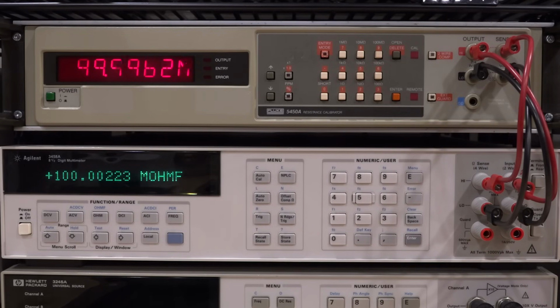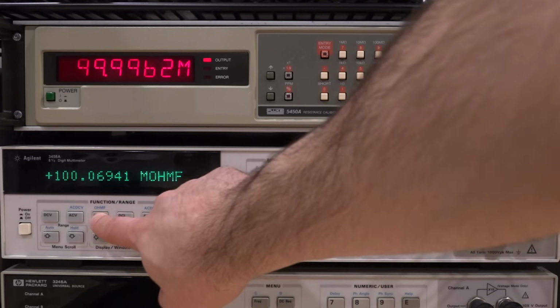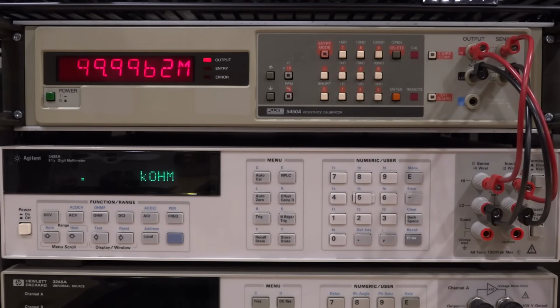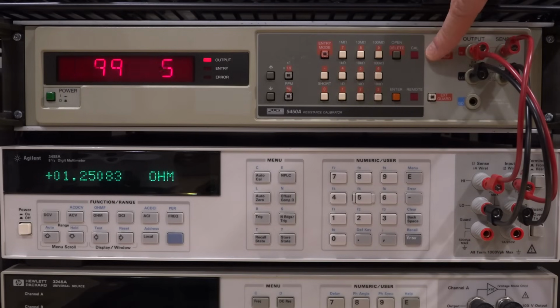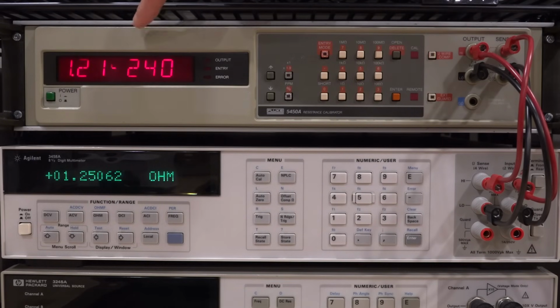This is a 4-wire measurement. We can also do a 2-wire measurement, but it shouldn't matter at this 100 mega ohm range, of course. There it is. You can settle it down. But if I go to 1 ohm, that will make a difference. You can see it should be over 1. There it is, 1.25. But if I enable the 2-wire compensation, this value will change. Now it should match more closely, and it's pretty close. I think the calibration probably wasn't lost.